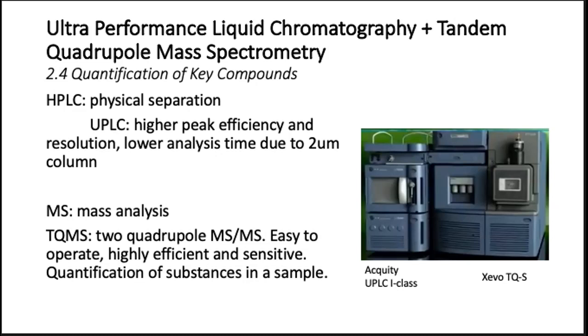An autosampler sends the sample to the column, which separates it, and finally to the detector, which receives the result of the sample separation. These results are translated in a chromatography data system, giving a chromatographic spectrum that provides quantitative and qualitative data about the sample. Peaks are plotted with respect to the retention time, and concentrations can be calculated. The UPLC has a few advantages over the HPLC, which derive from a difference in the column. The UPLC column has a mean particle diameter smaller than 2 microns, which results in higher pressure in the system and optimal linear velocities.